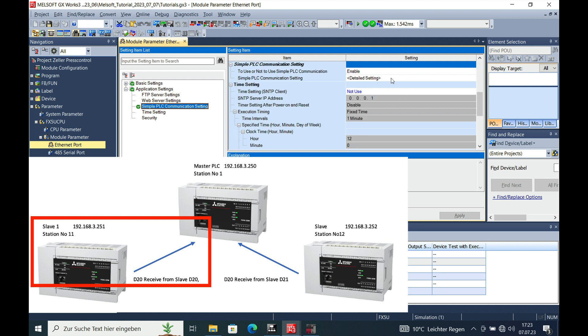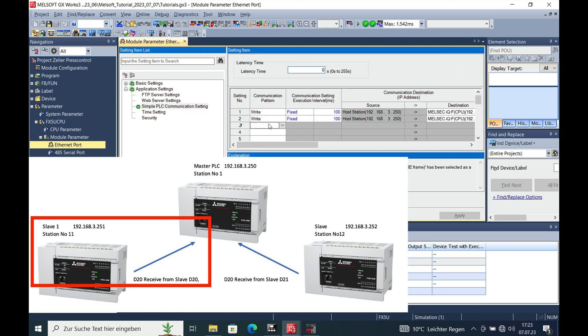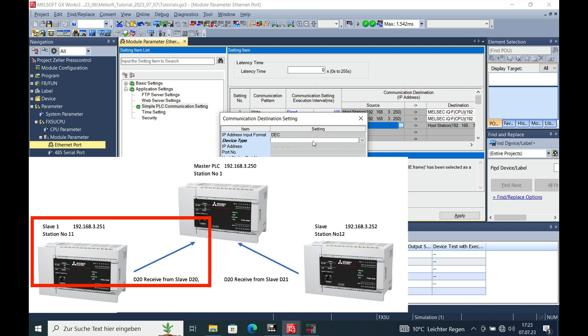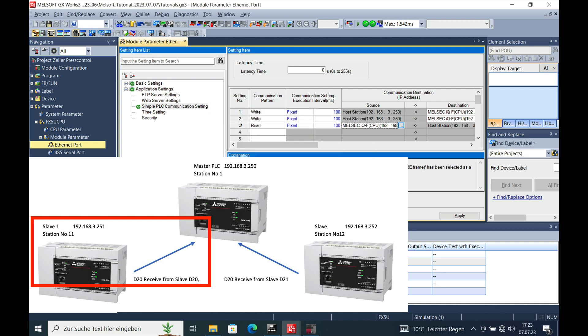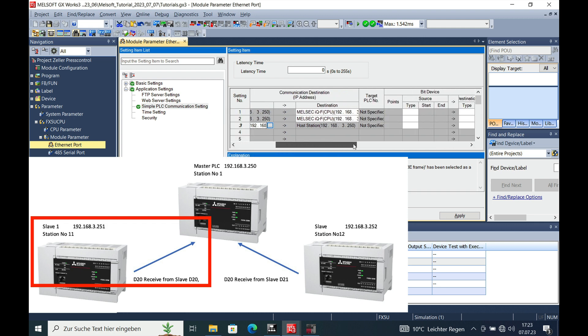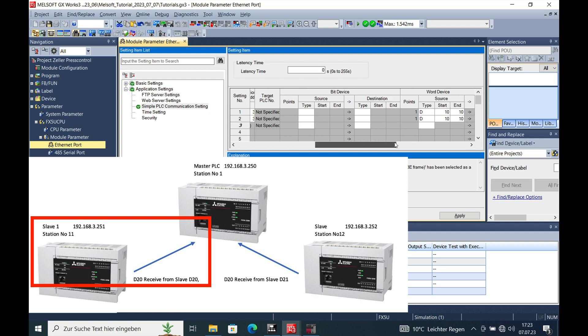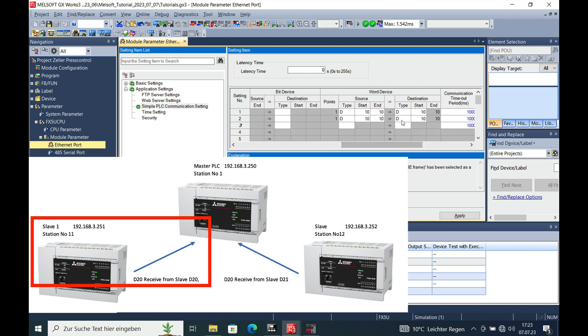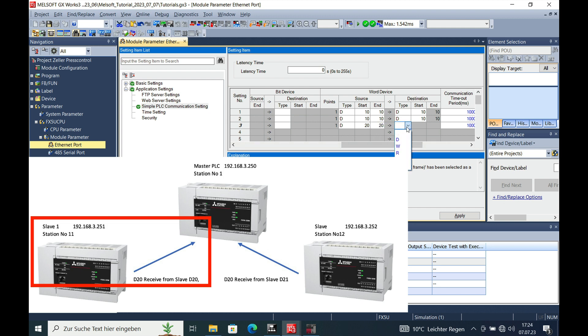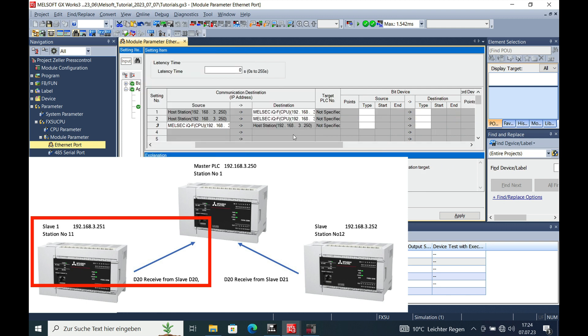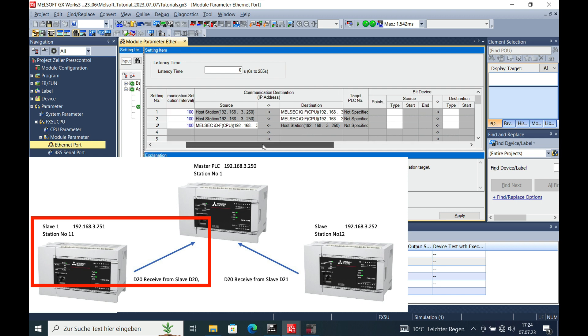Go to simple communication settings, to the detail settings again. And this time we will be reading from the Ethernet port, from slave number 1, which is the ending number 251. And we will be reading the D20, writing also only just one, D20. So writing it to the D20, the destination this time is our own PLC, that's why we can change this on here.